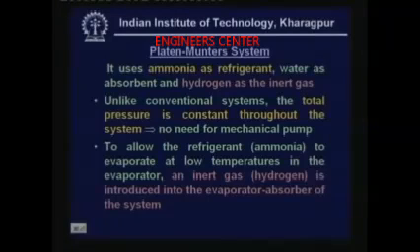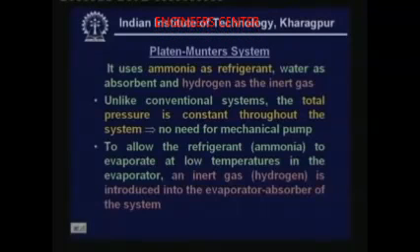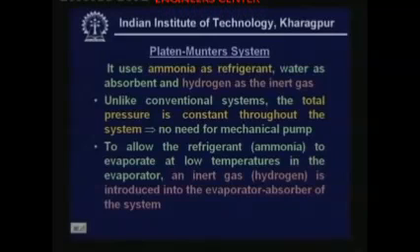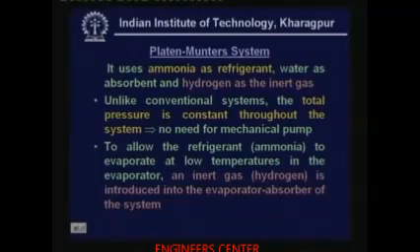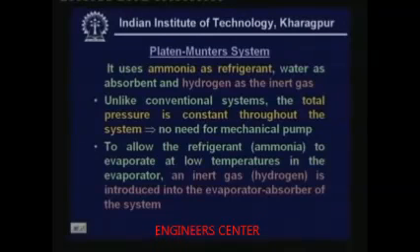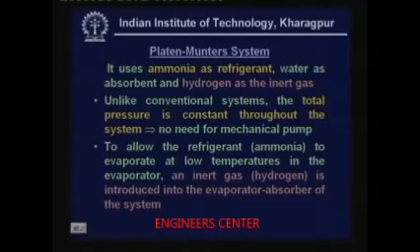To allow the refrigerant to evaporate at low temperatures in the evaporator, an inert gas is introduced into the evaporator-absorber section. When discussing Platen-Munters systems, you must make a distinction between total pressure and partial pressure. The total pressure is the same throughout the entire system, but the partial pressure will be different at different locations. In the evaporator section, P_total equals P_ammonia plus P_hydrogen.